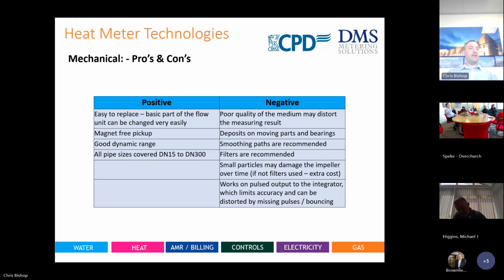With large deposits in a system, large particles, because it's a moving part, you can get situations where that can damage the actual turbine inside. Then there are straight pipe runs, which relate to your designs, because you have to design for more straight pipe inside your systems. Instead of going for 3 diameters before and 3 after for the more sensitive meters, you have to go down the route of 10 diameters before and 10 after. So you're installing more pipework at more cost, but with no benefit at all, because it's a mechanical meter that shouldn't really be installed in heating systems. So it's that sort of mentality to think about with regards to design.